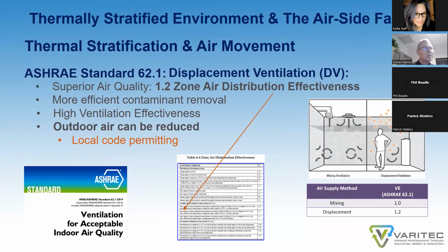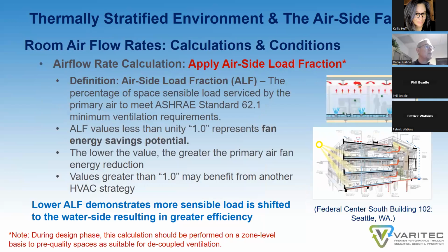If a building is being designed with this technology, it can apply a 1.2 zone air distribution effectiveness, which means that you can reduce your outdoor air levels by 20%, which you may or may not want to do depending on what the owner is looking for in the building, but that opportunity is there. And the reason why I included this slide specifically was to demonstrate ASHRAE's recognition of displacement ventilation and thermally stratified environments as being conducive for creating better IAQ.